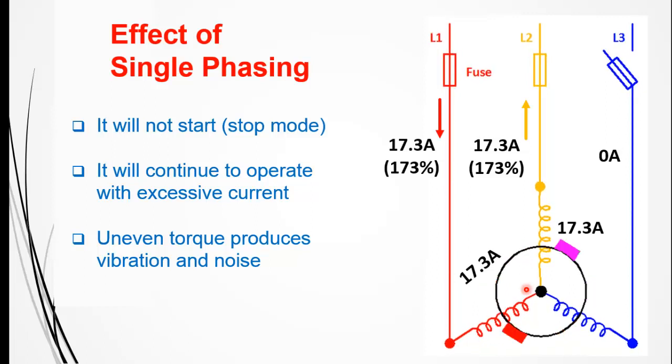To avoid the single phasing problem, we must install phase failure relays which will sense the phase failure and trip the entire circuit, stopping the three-phase motor. I hope you understand clearly the concept of single phasing problem. For more interesting videos, stay tuned and don't forget to subscribe to our channel. Thank you for watching.